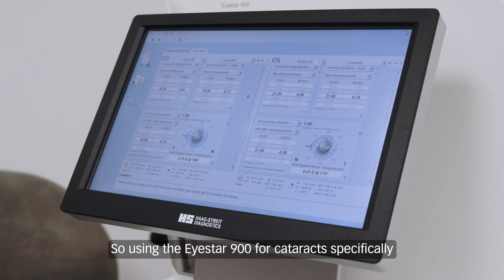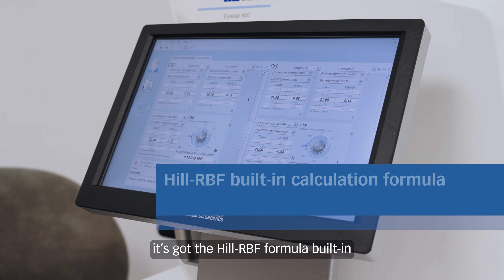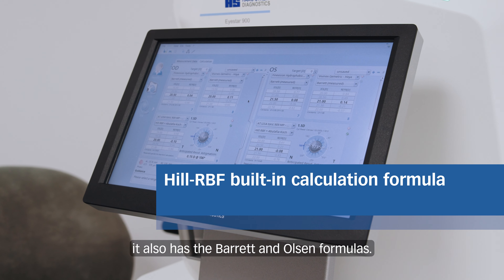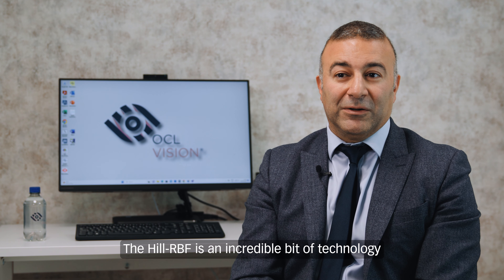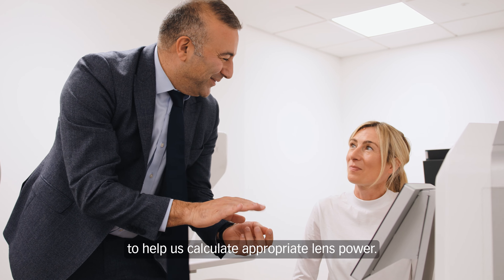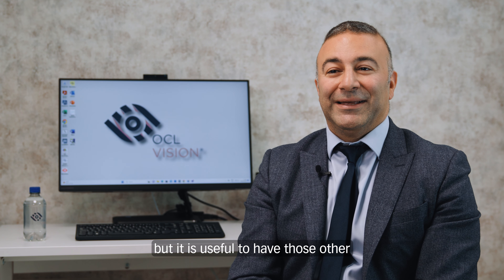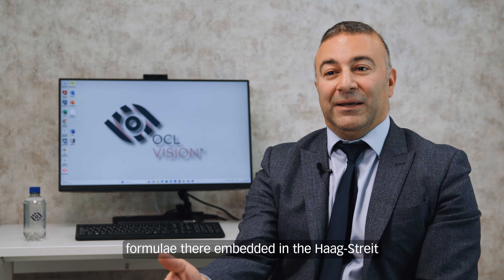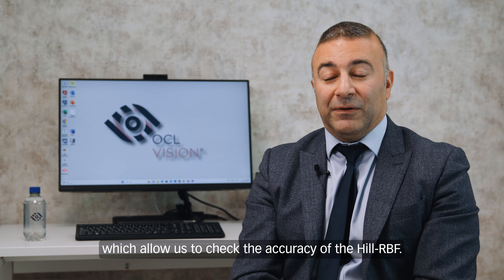Using the Eyestar 900 for cataracts specifically, the software is incredible. It's got the Hill RBF formula built in, as well as the Barrett and Olsen formulas. The Hill RBF uses artificial intelligence to help us calculate the appropriate lens power — personally I think it's the best thing on the market — but it is useful to have those other formulae embedded in the Haag-Streit software, which allow us to check the accuracy of the Hill RBF.